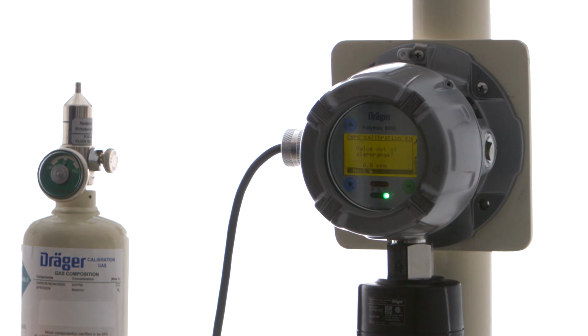So now it's asking us if the value is out of alarm range. Obviously 0 ppm is out of alarm range. We're going to select next, and now we're back to our calibration menu. So now zero calibration is done.